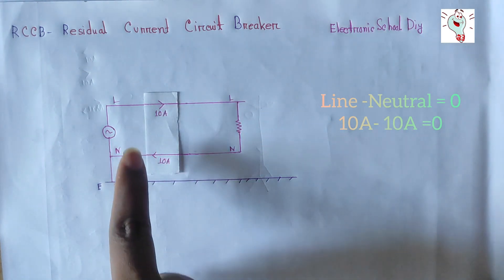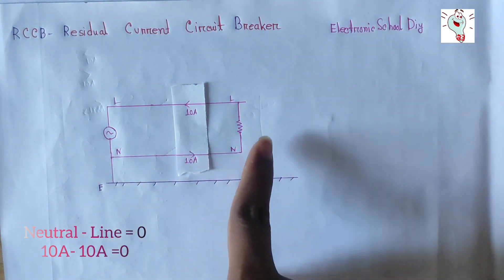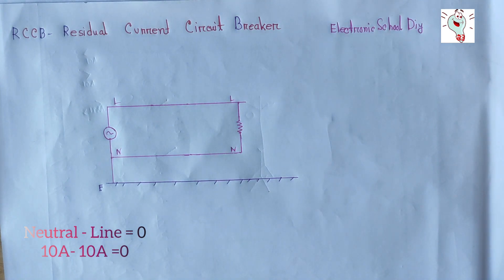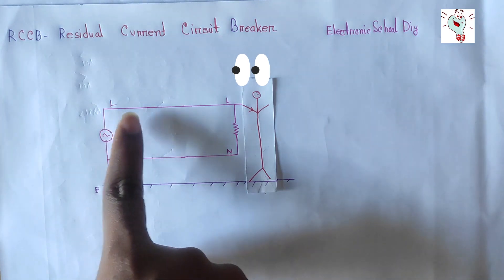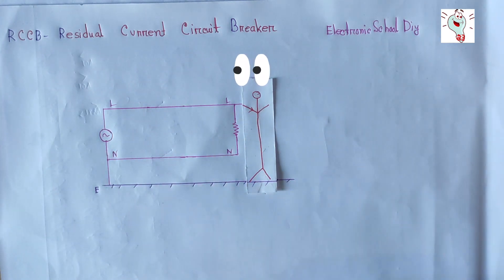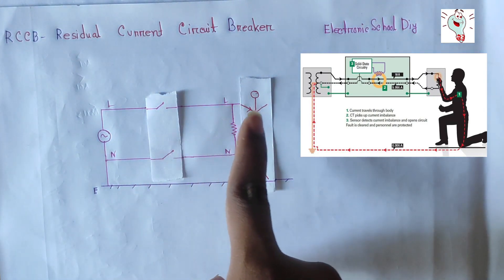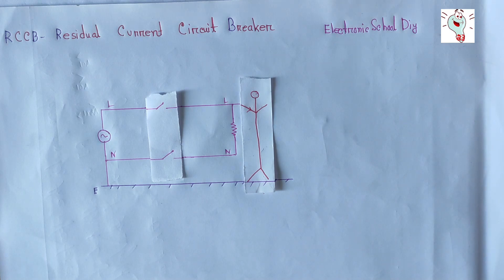Let's get familiar with the RCCB. The electrical wiring device is designed to quickly and automatically isolate a circuit when it detects that the electrical current is unbalanced between the supply and return conductors. For example, when the current flowing through the line to neutral is balanced — say 10 A on the line and 10 A on neutral — the current difference is zero and the device does not trip. However, when a person touches a live wire, current flows through the line to ground, and the RCCB detects the unbalanced load and cuts the output.